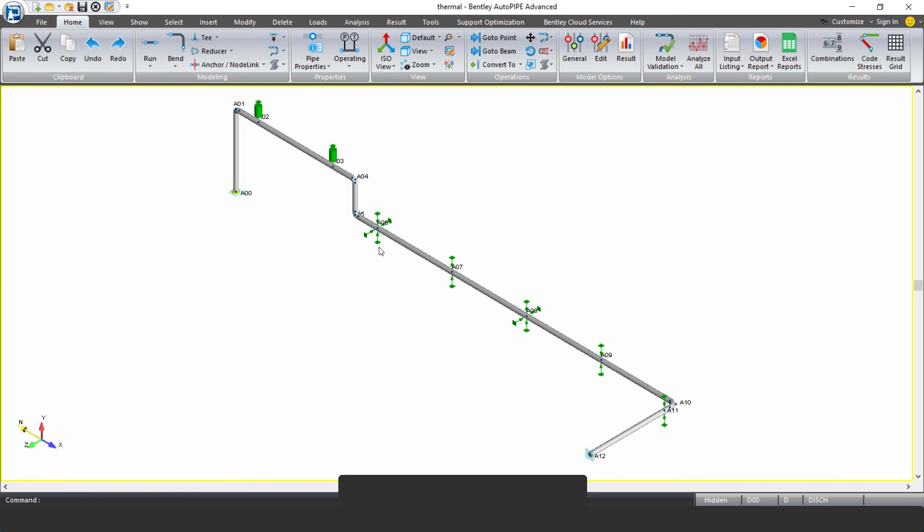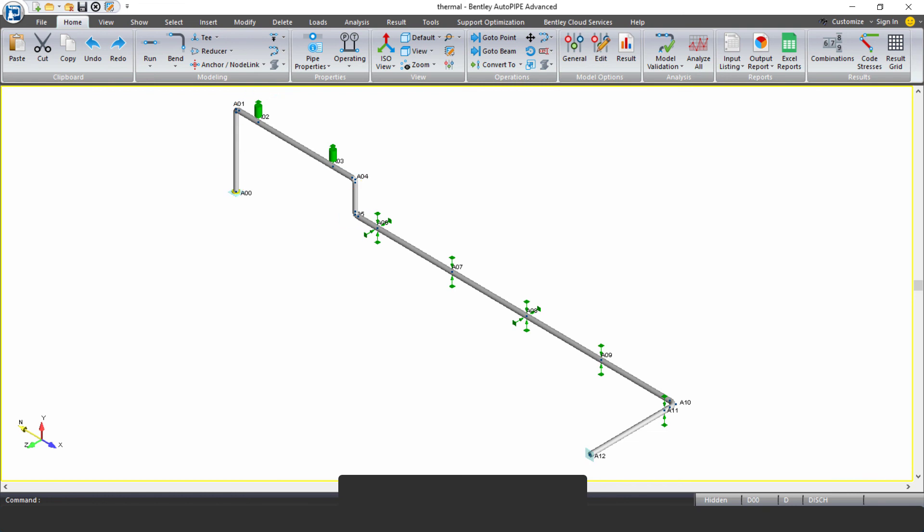So just looking at this, knowing that it's fairly hot, when we run the analysis, very simple analysis, just gravity temperature pressure, we could pretty much look at this and determine in what ways is this flexible. Well, first of all, this area is more flexible because we have springs and that is the entire purpose of putting in our springs is that it does allow it to grow thermally. So we're allowing it to move upwards along these vertical sections here. The other way that it's flexible is that we do have guides and vertical support. So we're keeping the pipe up. We're trying to stop it from moving laterally along that long line, but we're not stopping any axial growth. So we can grow this way out of here, nothing stopping that. And we can grow this way along this long line of pipe, nothing is stopping that, right, except for the very end anchors.